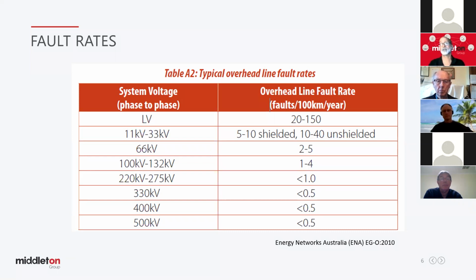That zone substation has half a dozen or 10 feeders going out to feed your pole subs, your street subs, pad mounts. If that was 11 or 22 kV, a common distribution voltage in a lot of our states, the fault rate could be, for unshielded feeders, and not many of these feeders are shielded in the streets, 10 for the southern states with less lightning around, or 40 up in the northern states with a lot more lightning. It's a lot more likely for a lightning strike to cause a flashover and then a follow through of your power frequency.